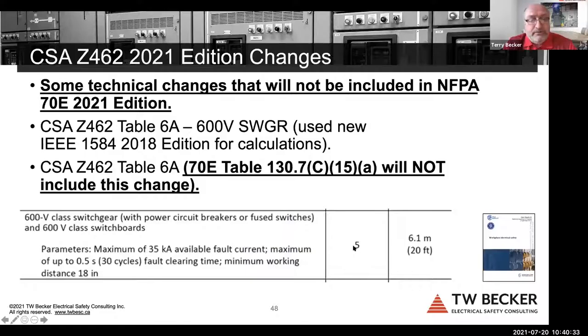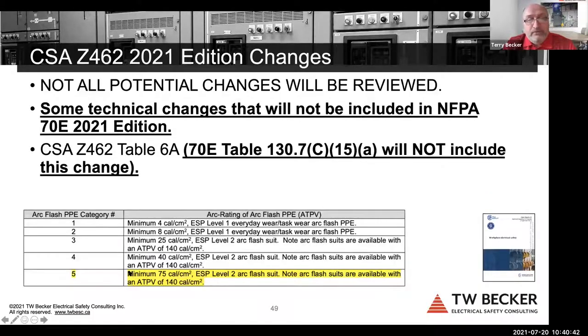So we created arc flash PPE category 5 and added that to our Table 6C, right? None of this is in 70E. And now there's a new category 5, minimum 75 calories, right? So this is a huge, significant technical divergence. And I don't know if it's going to be in 70E in the 2024 edition. I guess time will tell that story.